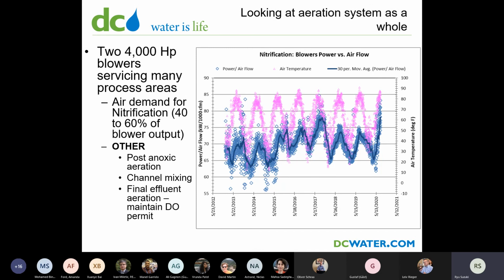Another challenge that we have is shown in this busy graph, which is looking at the blower efficiency since 2012. On the purple line, what you see is the air temperature. You see it going down in the winter and going up in the summer. These blowers tend to be way more efficient during the colder weather and less efficient during the summer. But what's hidden in this trend is that not all summers we get the same efficiency. And it's interesting to see that this particular summer, we were getting the poorest efficiency, when you measure it as the amount of power required to deliver a certain amount of airflow.